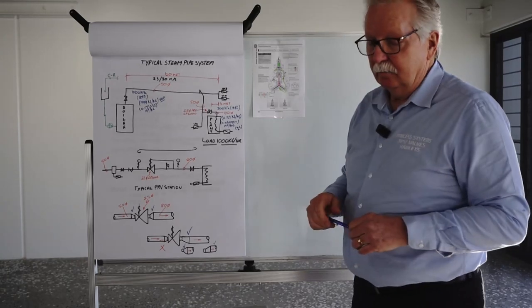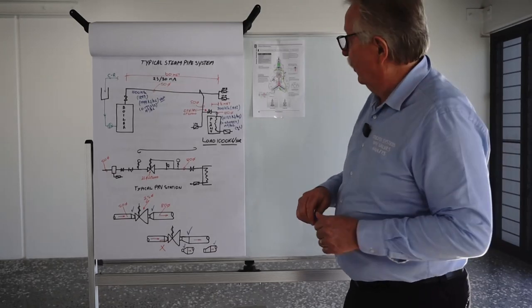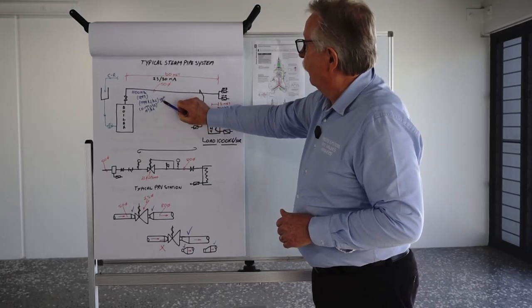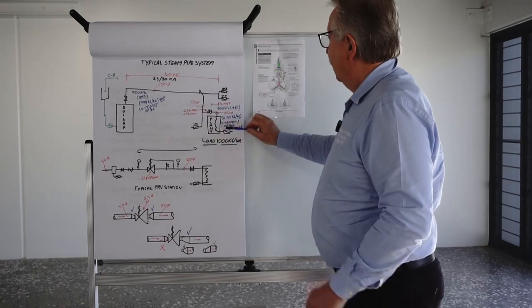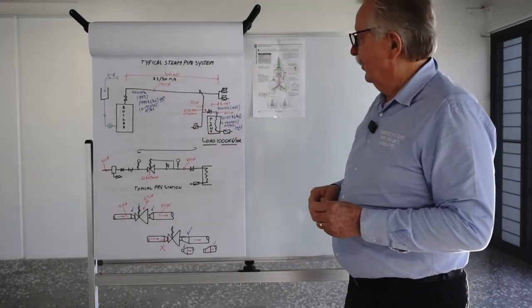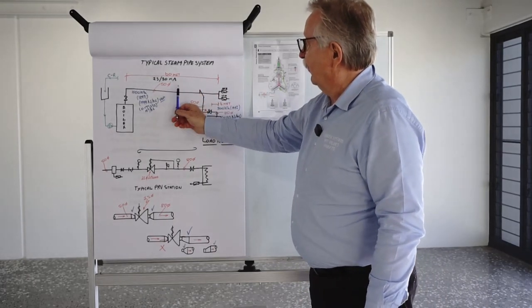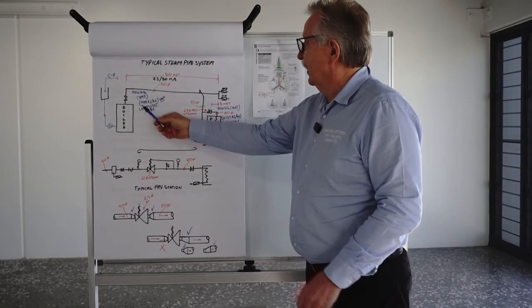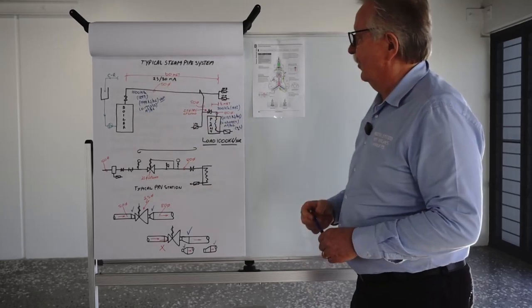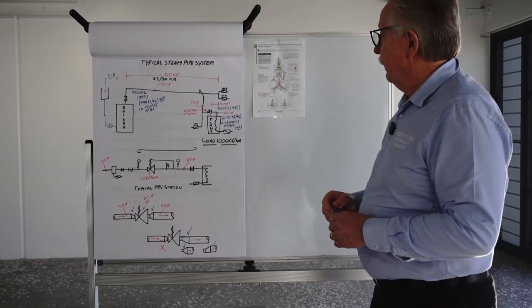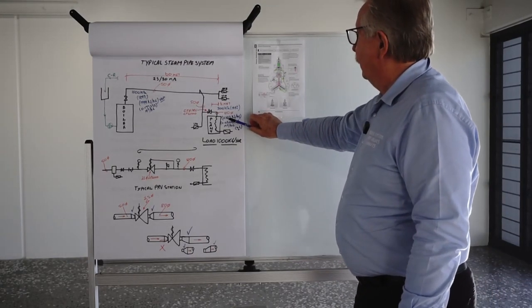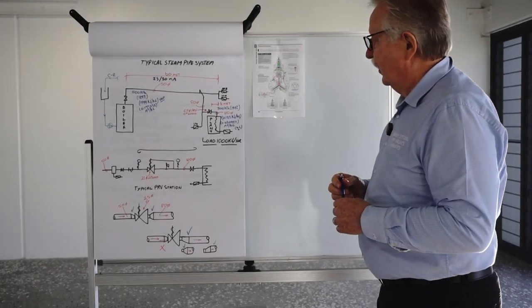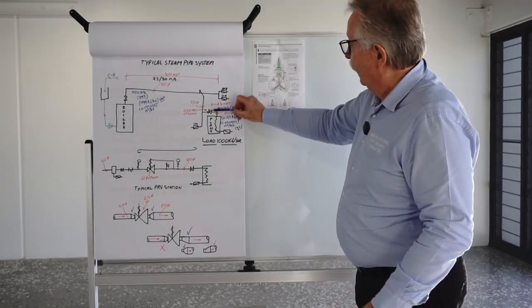When I was talking about heat transfer, I think I mentioned heat transfer before, as well by reducing pressures or changing pressures you have a difference in enthalpy of vaporisation. And there is more enthalpy available for use at the lower pressure than there is at the higher pressure. If you look at the steam tables, you'll see that the 1000 kPa at 184 degrees C has an enthalpy of vaporisation of 1999 kilojoules per kilogram. And at 300 kPa, it goes up to 2133 kilojoules per kilogram. So there's more effective enthalpy of vaporisation for your heat transfer process in your plant.